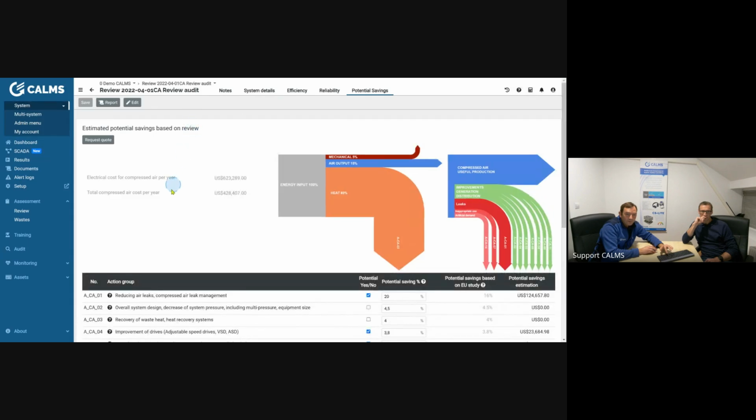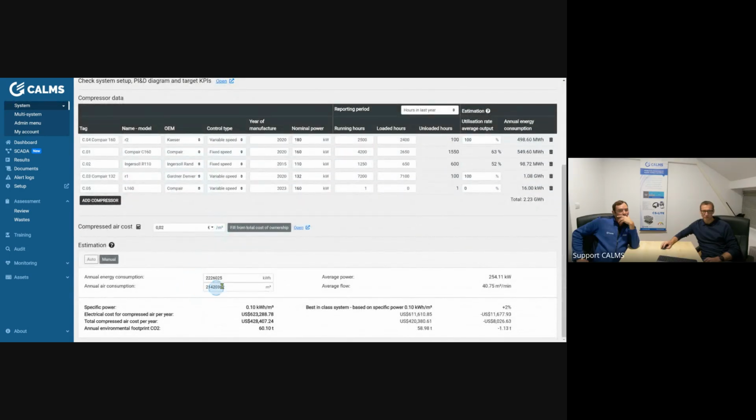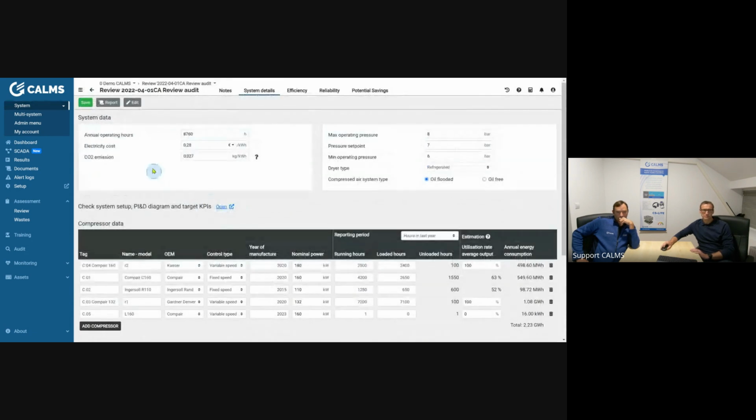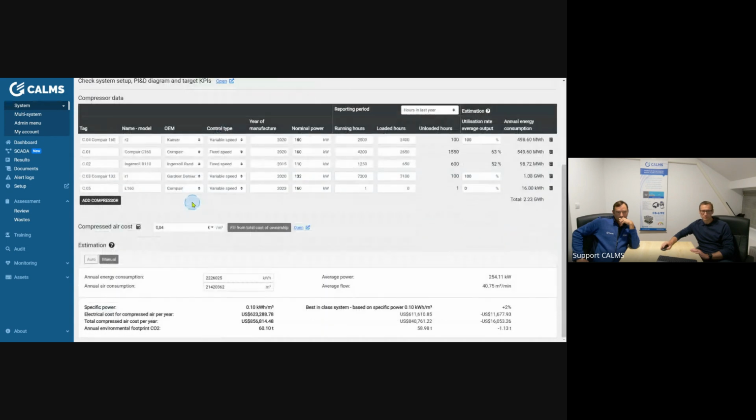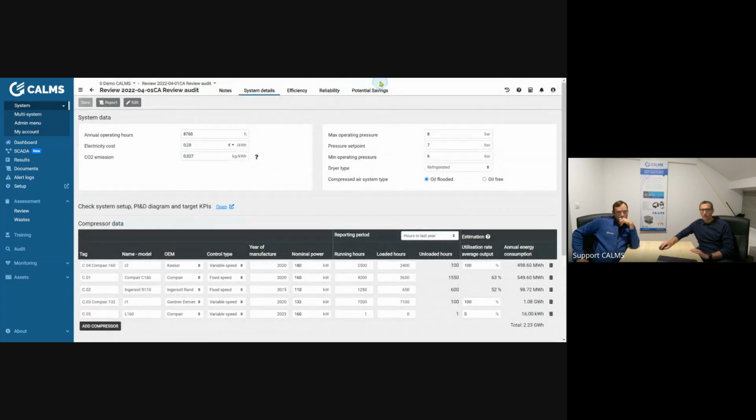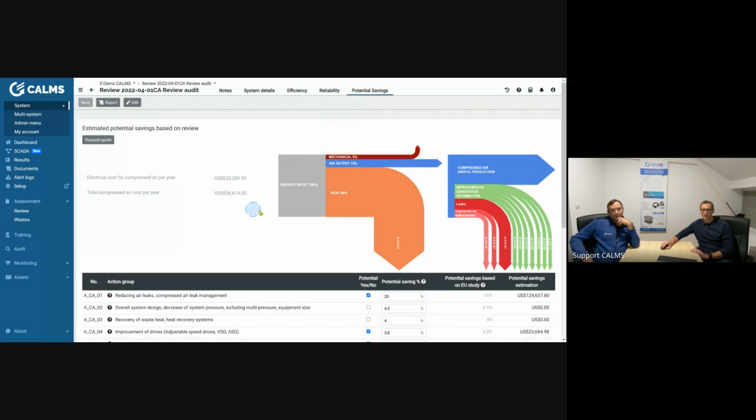Has somebody in the webinar found a bug? So I think you have. No. You think no? No. Because of heat recovery, maybe. Because of heat recovery, no. I think the only problem is actually here when we compare this cost of electricity and the cost of compressed air. It is 0.4 maybe. I think we found it. And now this is compared to the cost. This is the more real cost for the compressed air per cubic meter. Sure. And this is now 600 and 800, the compressed air cost. And this is the actual realistic one. Yes.